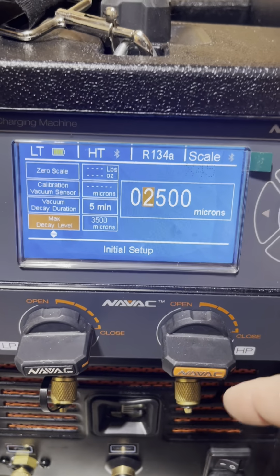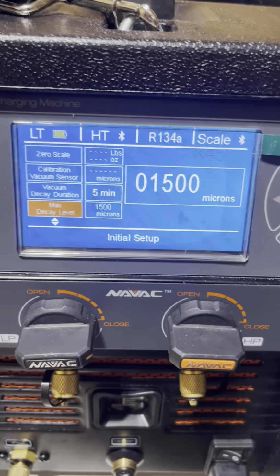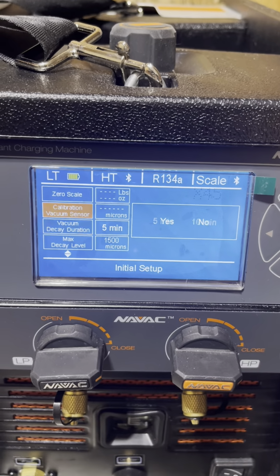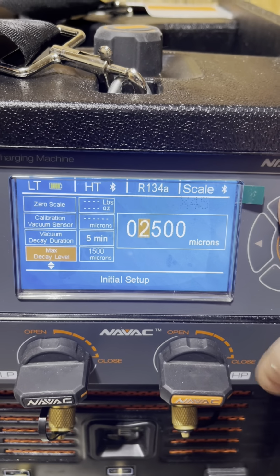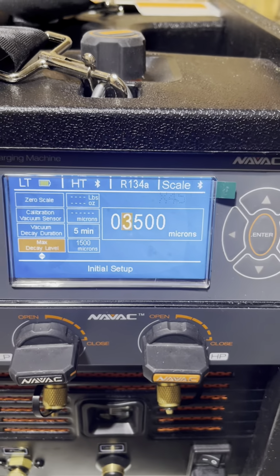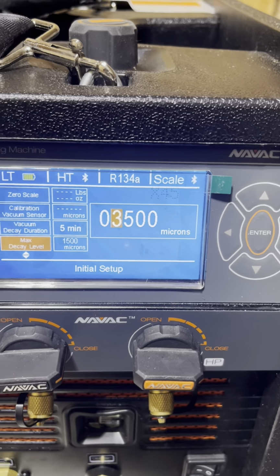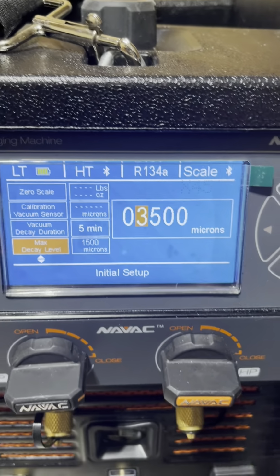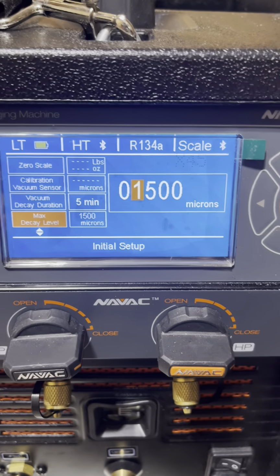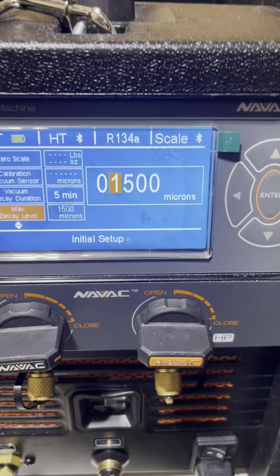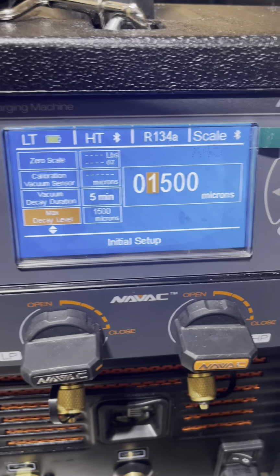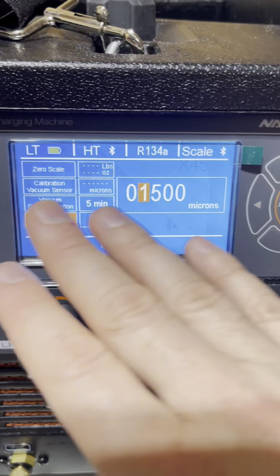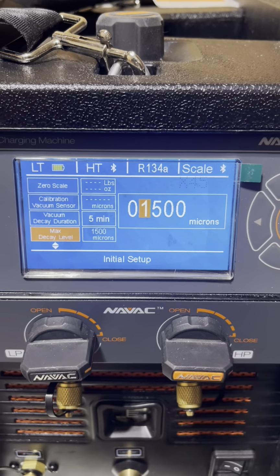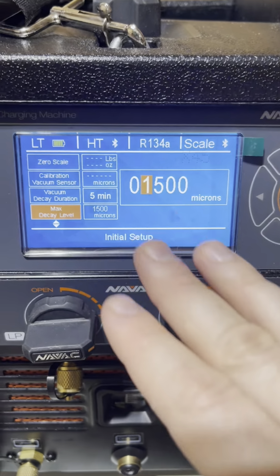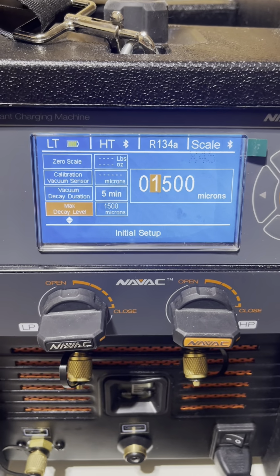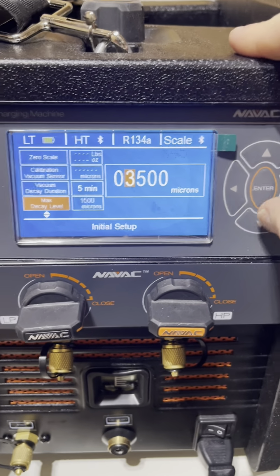You can do 2500, you can do 1500. It's really up to you. I realized that for me 3500 works the best because some systems are not really accurate. I don't know how accurate this machine is, but I tried 1500 and it sometimes failed, and then I thought maybe I had a leak somewhere, so I checked it and there was no leak. So I don't know if the pressure sensor here is really accurate or not. I'm still testing the machine, but I think for me 3500 is the best.